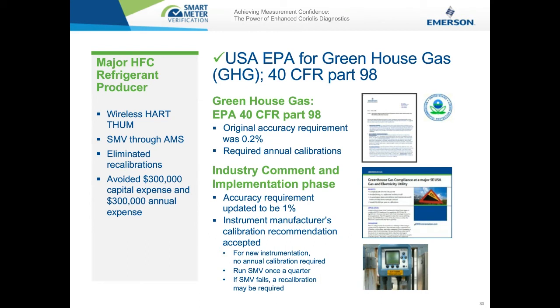The accuracy required in those devices is typically not as stringent as a Coriolis meter could offer, but one of the things that we discovered is using more traditional flow measurement technologies such as orifice plates. Those plates would have to be physically inspected and photo documented every few years. Now, you all know that most of the orifice plates in use in industry are bolted in line. You're not using senior orifice type fittings where the orifice plate can be removed while you're flowing. So from an operational point of view, compliance became a real sticky point for these users.